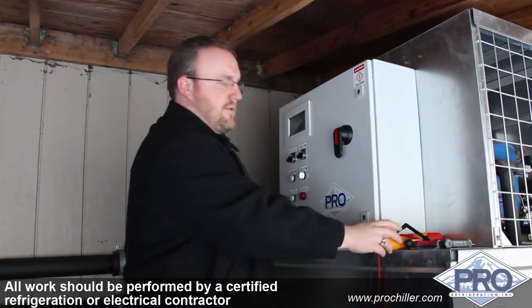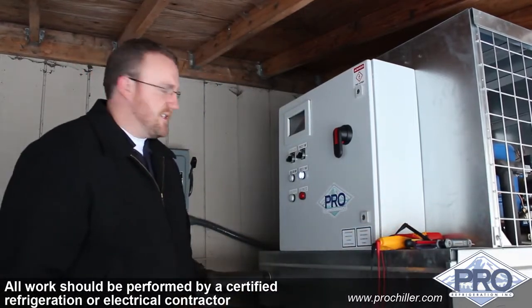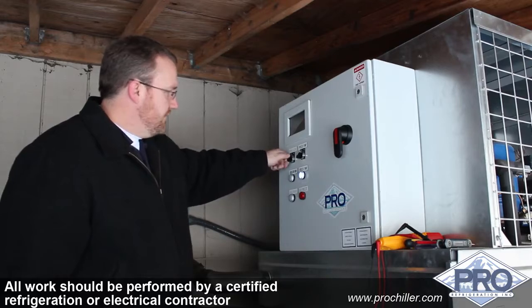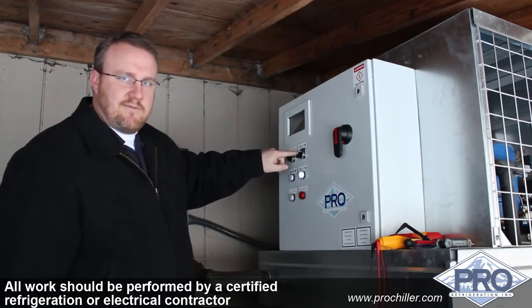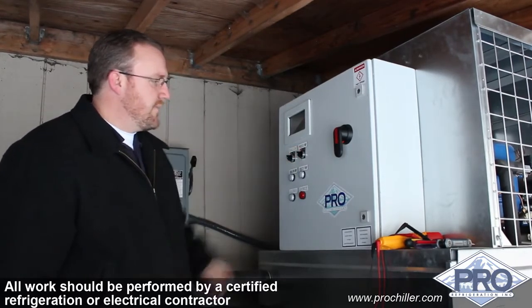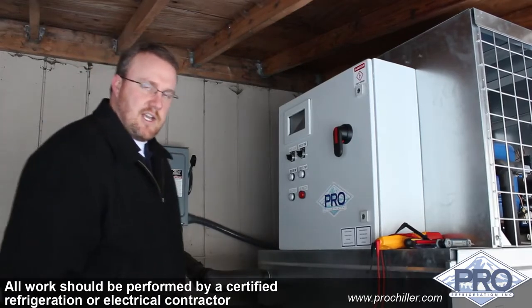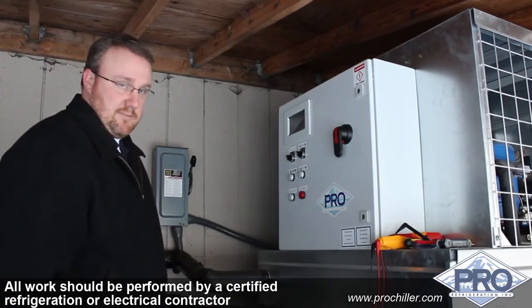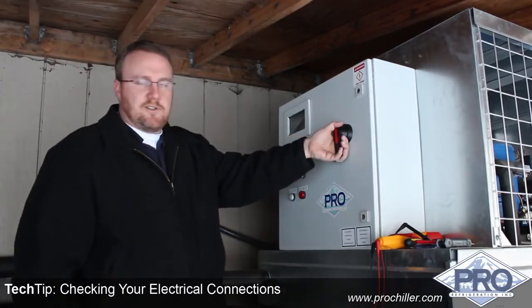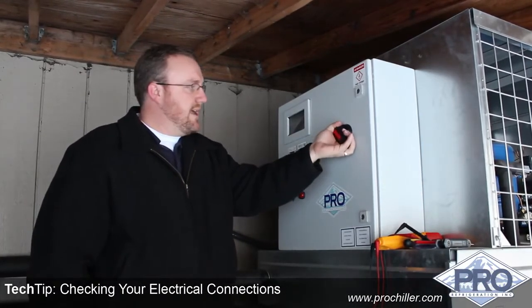First thing we're going to do is shut off the chiller system. We're also going to shut off the process pump. Now with everything off, we're going to shut off the main electrical supply here, and also shut off the disconnect on the electrical control panel.